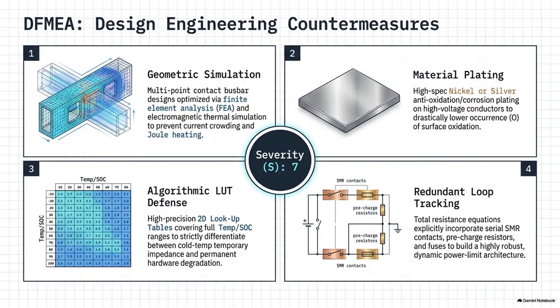What do you mean? According to Holm's theory of electrical contacts, when two nominally flat metal surfaces are bolted together, they only physically touch at a few microscopic asperities, the absolute highest microscopic peaks of the surface roughness. Oh, like two mountain ranges pressing together. They only touch at the peaks. Exactly. So the electrical current, instead of flowing evenly across the entire surface area of the bus bar, is forced to squeeze through these tiny microscopic bridges. And that bottleneck causes heat. Massive current crowding. It's known as constriction resistance. All the current bottlenecking at these few microscopic points generates intense localized heat.